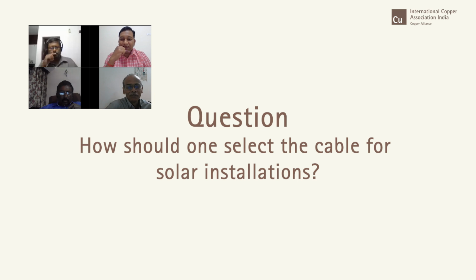I am not an expert in cables, but whatever little I know, I will share. I think as a practicing entrepreneur and established solar professional, Mr. Sivaram Krishnan will be able to provide the right answer and recommendation. But all I know is that cable insulation being an organic material, when it is exposed to heat it will first start softening, and beyond that point it will start releasing toxic gases. So one is the impact of the toxic gases itself, and the impact of any chemical incident taking place, which can lead to disastrous consequences, and then the consequence of the insulation itself getting derated and causing fires. So you have to really see, as I understand, I may be wrong.